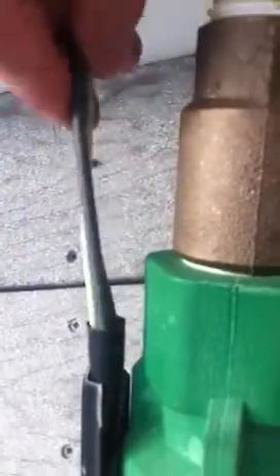We want to make sure any place that the wire makes a sharp bend, there's a point of abrasion there where it could, if it moves around much, abrade the insulation on the wire and possibly cause the wire to wear through. But even with that said, if we were to just tape this just like it is, like I've got my hands, we've got this wire that's thinly insulated and poorly protected going up against this check valve, across the hose clamps, and then up the pipe to the heat shrinks, which are further up.